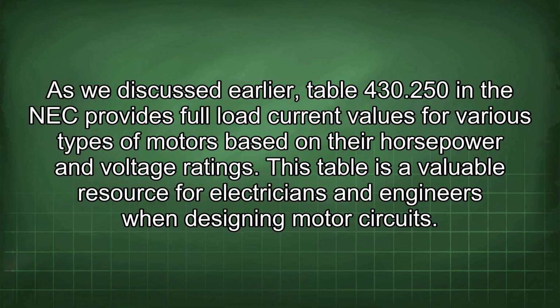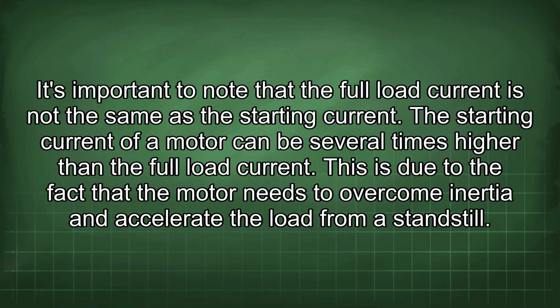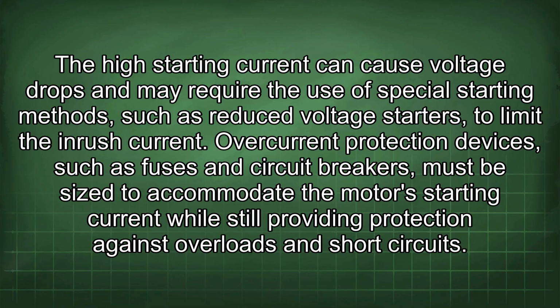As we discussed earlier, Table 430.250 in the NEC provides full load current values for various types of motors based on their horsepower and voltage ratings. This table is a valuable resource for electricians and engineers when designing motor circuits. It's important to note that the full load current is not the same as the starting current. The starting current of a motor can be several times higher than the full load current. This is due to the fact that the motor needs to overcome inertia and accelerate the load from a standstill. The high starting current can cause voltage drops and may require the use of special starting methods, such as reduced voltage starters, to limit the inrush current.